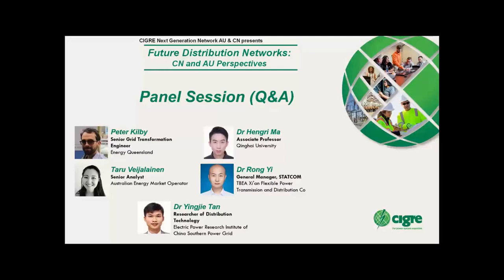So what we are exploring at this stage is, let me say, crazily upgrading the architecture of the distribution network. What we're thinking about is the idea of balance at different levels, balancing the demand and the generation from different levels. For example, at the distribution transformer level, we can say it's kind of a microgrid.